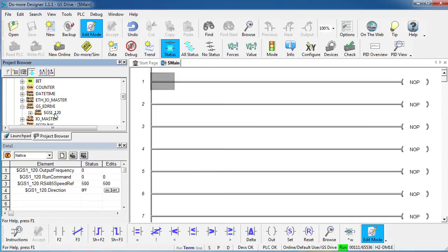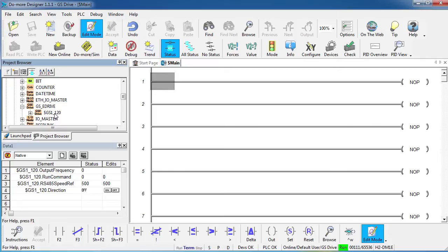Normally, we would do a Modbus write or just enter it directly into the drive via the front panel buttons, right? And since we usually set lots of parameters just to ensure everything is exactly the way we want it, that equals lots of Modbus reads and writes and or lots of manual entries. Wouldn't it be great if you could do your drive initialization with just one command? Well guess what? Ethernet IO has dedicated GSDrive commands that do exactly that.